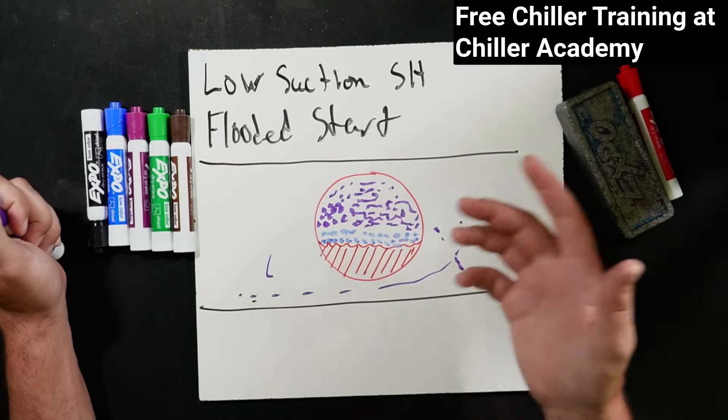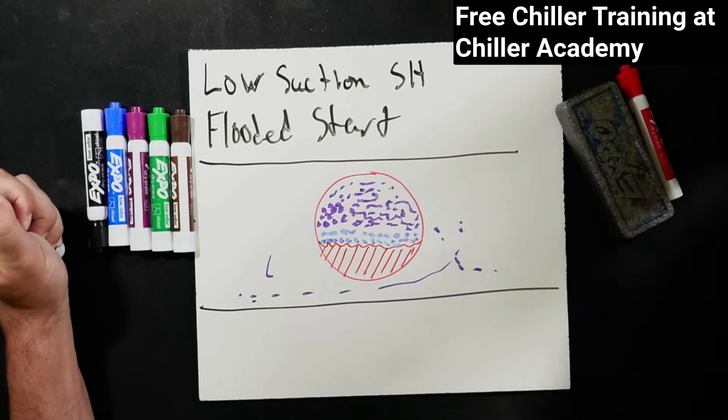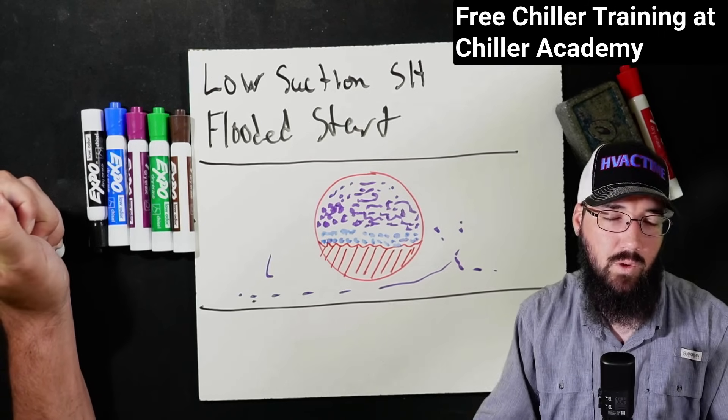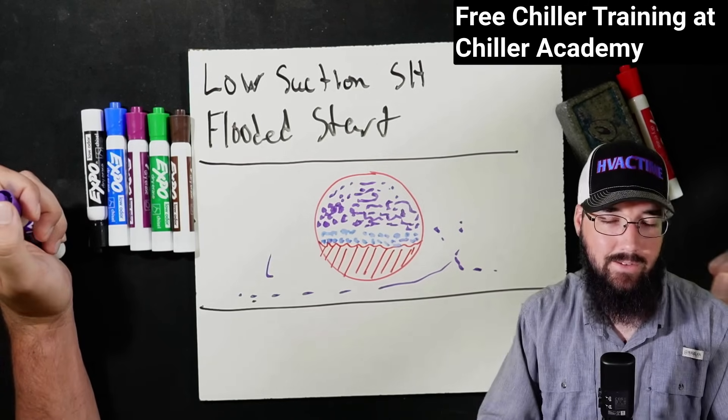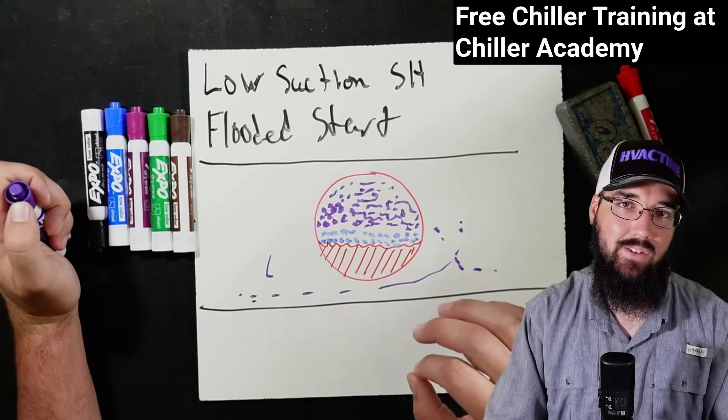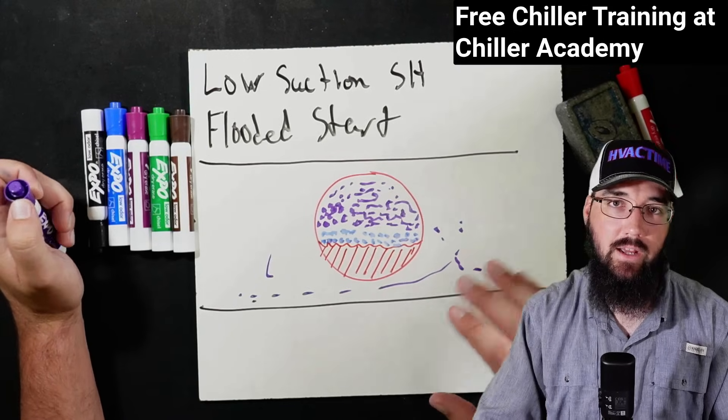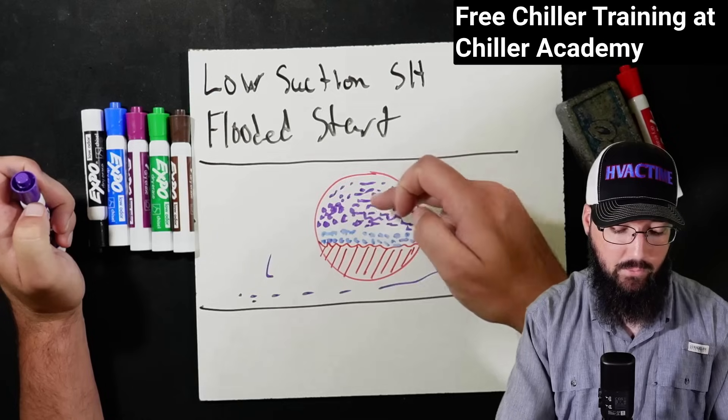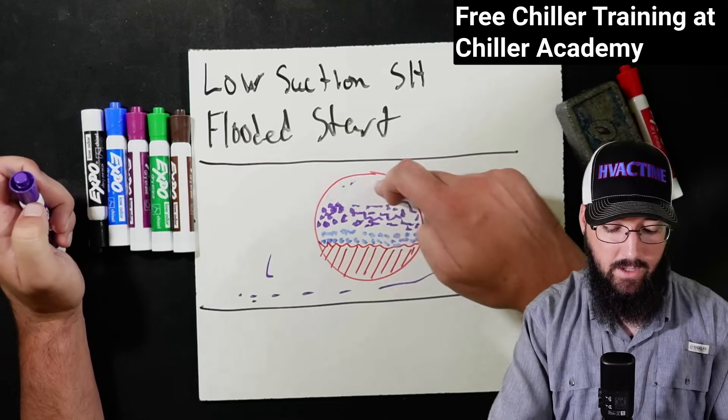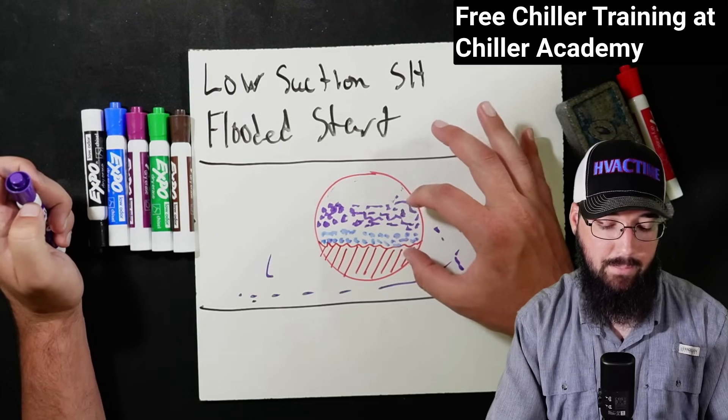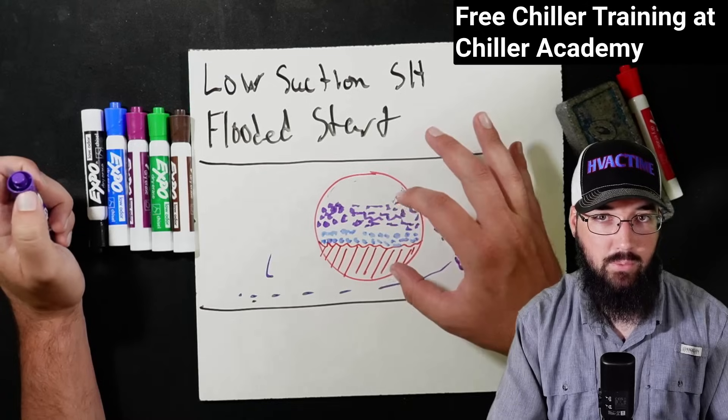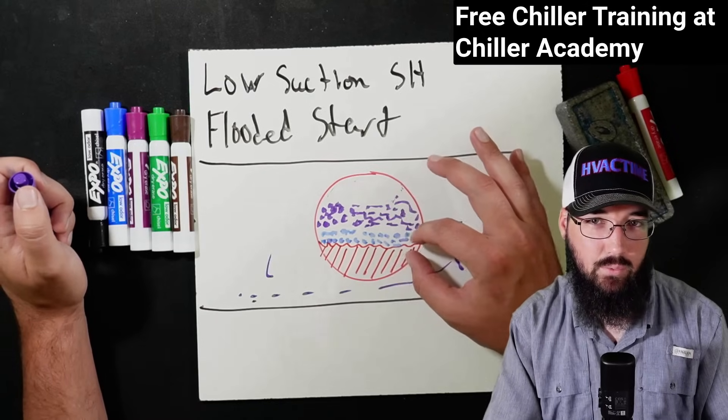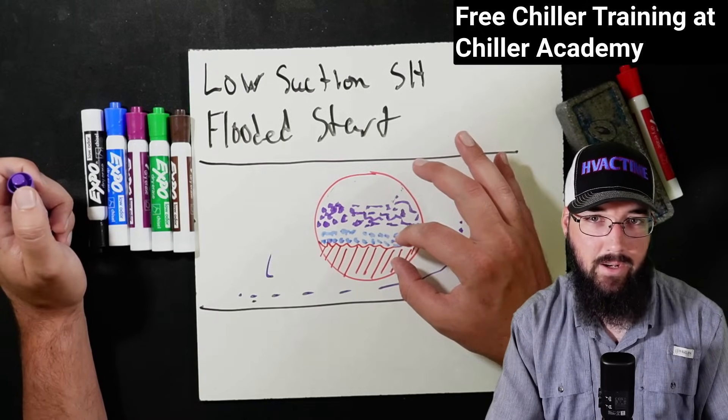I would consider that perfectly normal. I wouldn't be worried about that. It's when this escalates to the whole sight glass where a large portion, it doesn't have to be the complete sight glass. If we get to where we've got a full standing column of foam happening like this, that's when I want to investigate. I just want a teeny little layer if I'm going to have any at all.